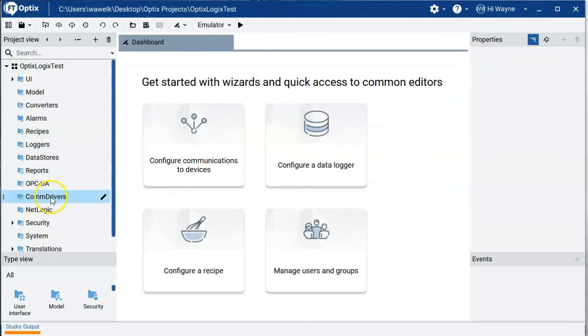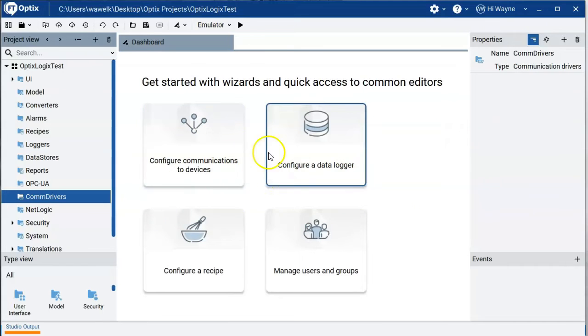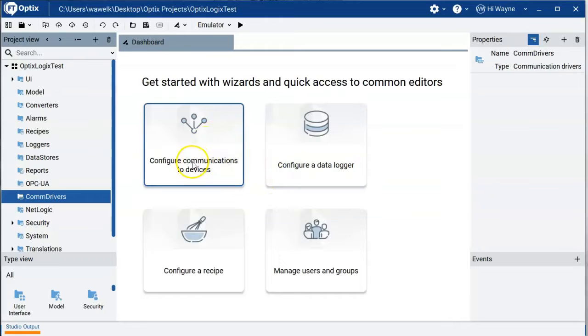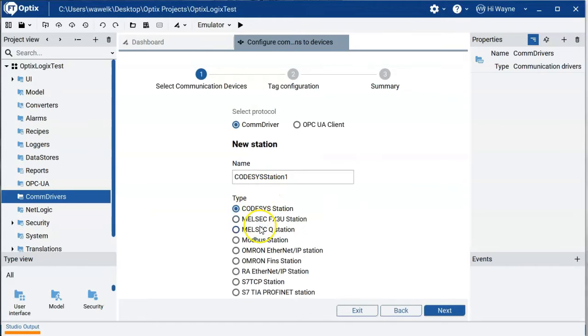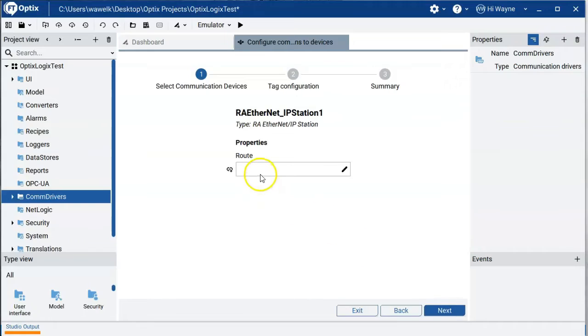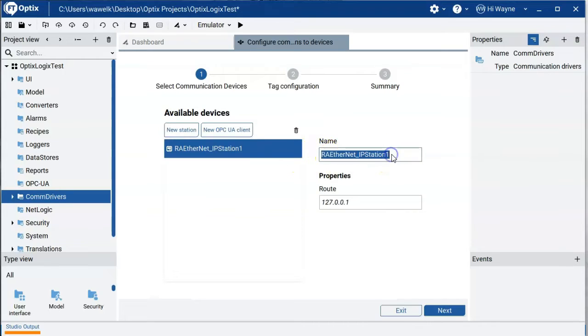To set up our COM driver, we can either right-click on COM Drivers in the navigation tree and select New > Rockwell Ethernet/IP Driver, or use the Configure Communications wizard. Using the wizard, we choose New Station, select RA (Rockwell Automation) Ethernet/IP Station, hit Next, and enter our IP address — which is the address of my Logix Echo emulator. I can give it a meaningful name, like 'Echo CPU'.